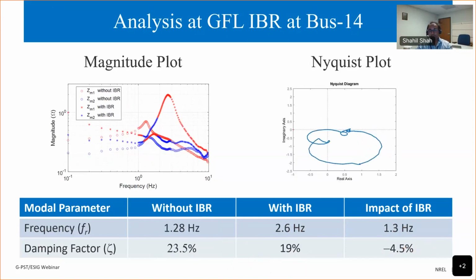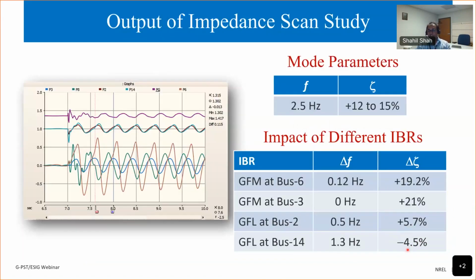In this analysis, we found that one IBR at bus 14, which is again grid following, is a negative contributor to damping. The system has higher damping when we remove this IBR, so it is contributing negatively to the damping. We can do this analysis at as many IBRs as you like and find out what the modes in the system are. Here I'm focusing on one mode, but we can perform the analysis at different frequencies depending on what you want to identify.